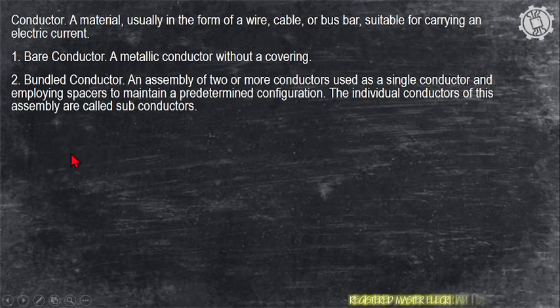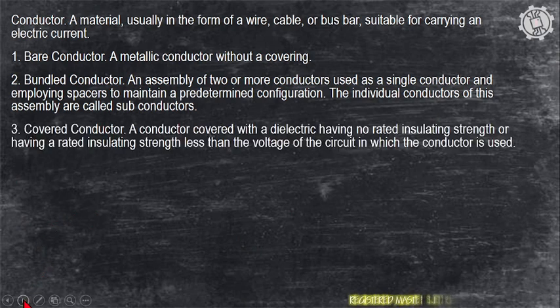So bundled meaning nakabundle yung ating conductor. It is an assembly of two or more conductors which are used as a single conductor. Covered conductor, a conductor which is covered with a dielectric having no rated insulating strength or having a rated insulating strength less than the voltage of the circuit in which the conductor is used. Pag naging covered, yung ating mismong conductor is covered siya, but the covering itself is not part of the wire. Hindi siya nakadikit dun sa ating conductor.